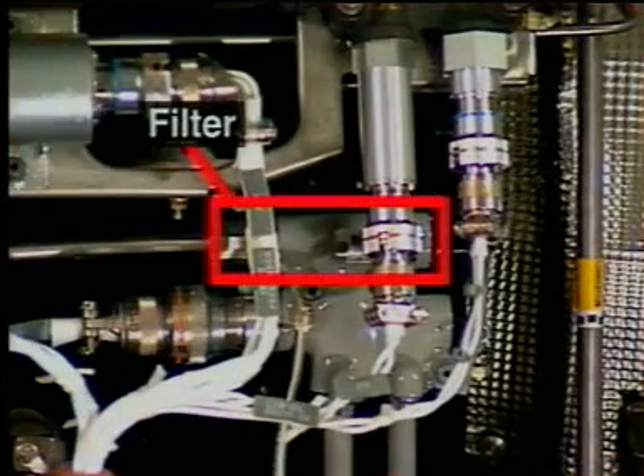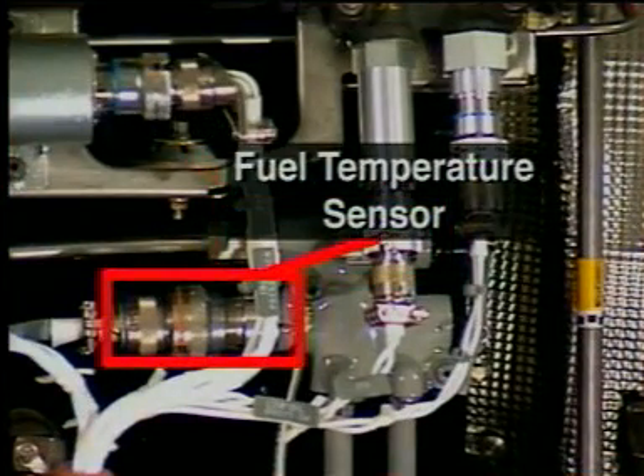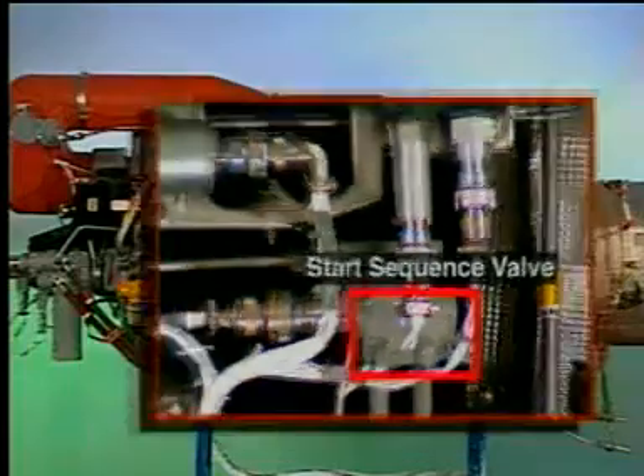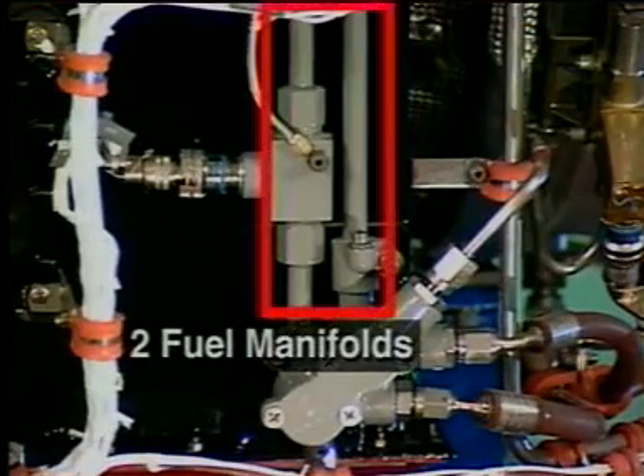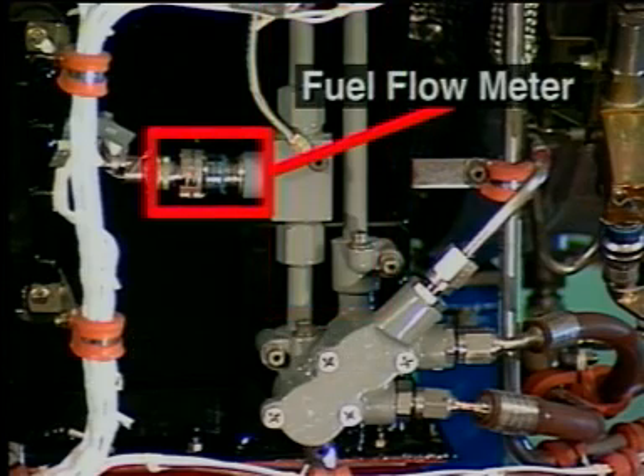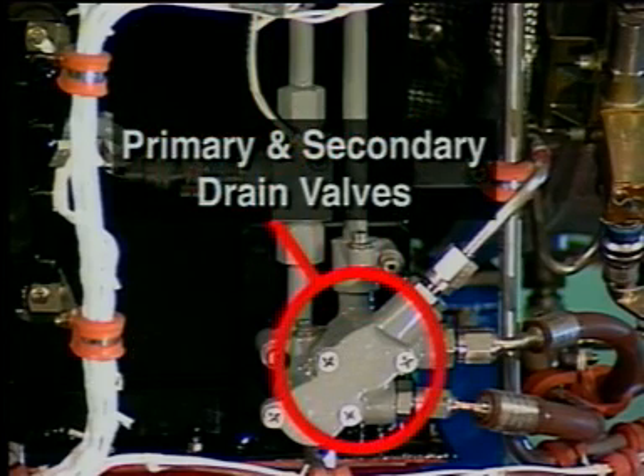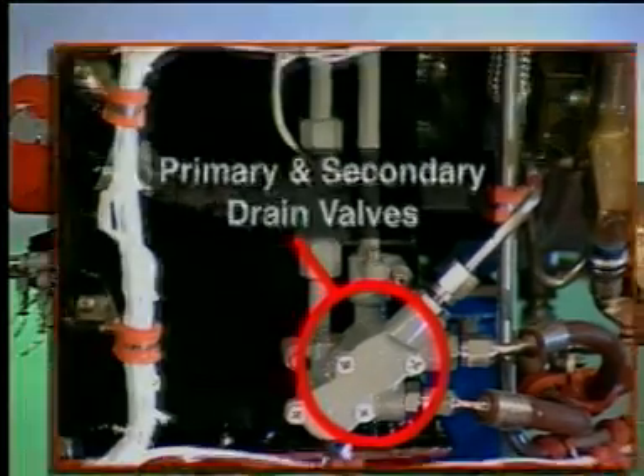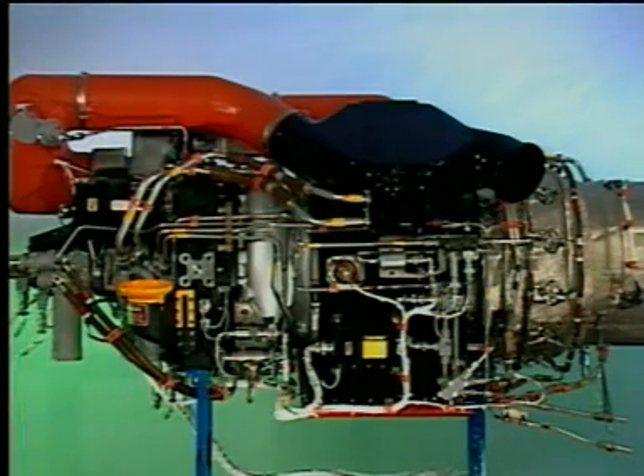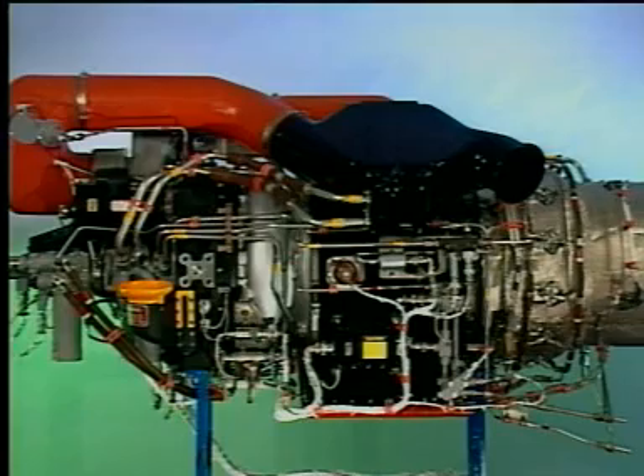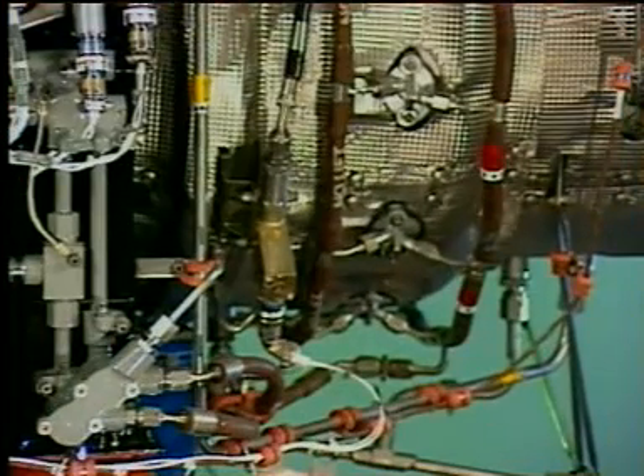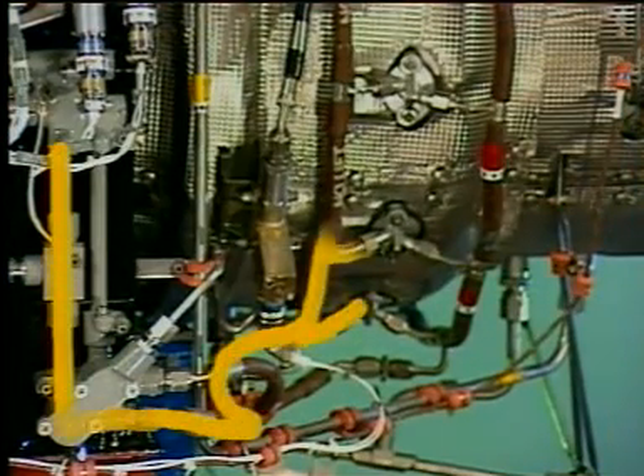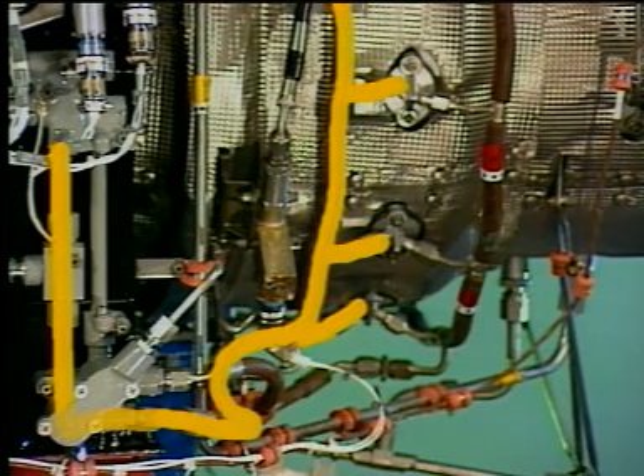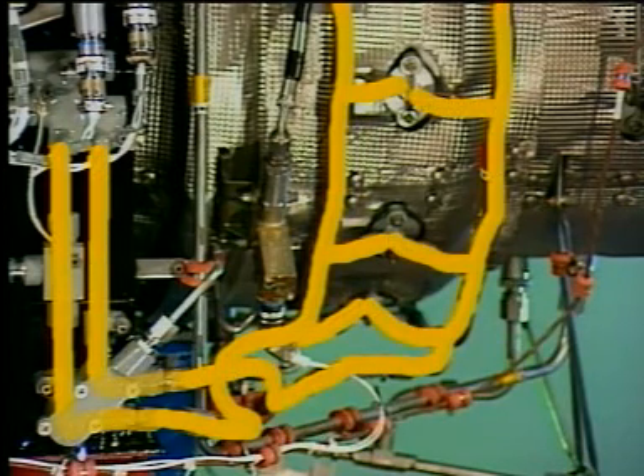This unit includes a filter, a fuel temperature sensor, a start sequence valve, two fuel manifolds, a fuel flow meter, and primary and secondary drain valves. The electronic control box uses fuel temperature and fuel flow data for fuel scheduling. During the initial start cycle, fuel from the primary manifold is supplied to the 12 dual flow fuel nozzles. When the back pressure increases, the start sequence valve opens and supplies fuel to the secondary manifold for acceleration and on-speed operations.